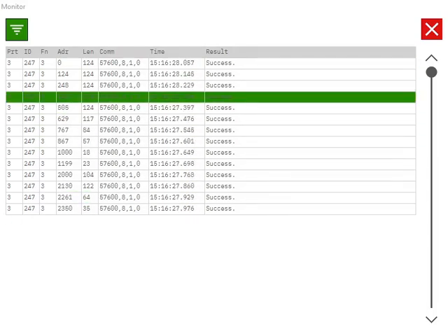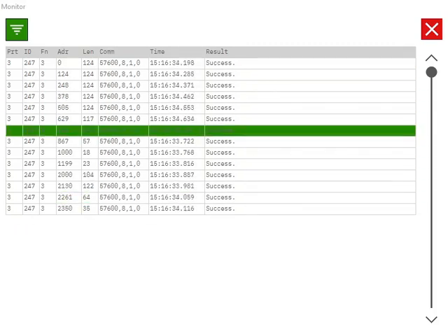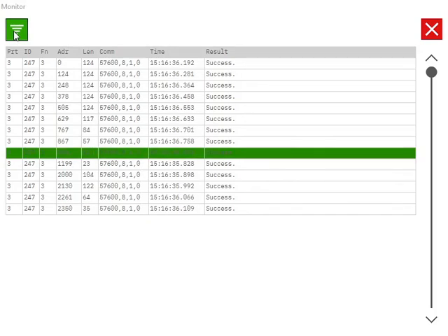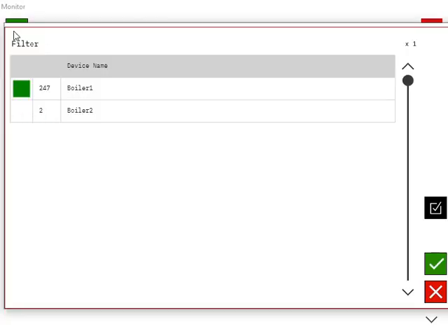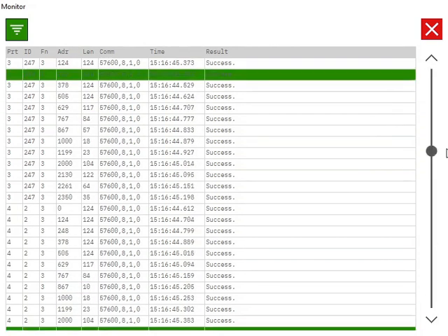However, NXTSD5 determines that communications is healthy after 3 successful consecutive messages. Again, this is a threshold designed to filter spurious communication issues. When everything is reading success, there are no communication problems.